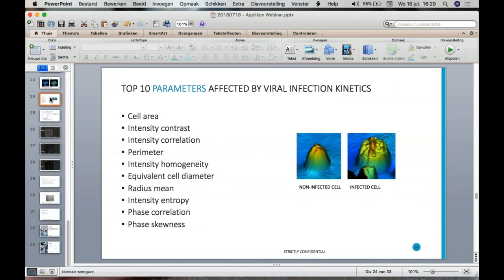Question: Is it possible to set time points for sampling? If so, what are the limitations? Yes — you can increase both the number of images taken and the time interval for each data point. Every 30 minutes is the maximum frequency, but you can easily go to every hour, every two hours, every three hours, or even once a day. We do advise keeping a minimum of 25 images per data point.